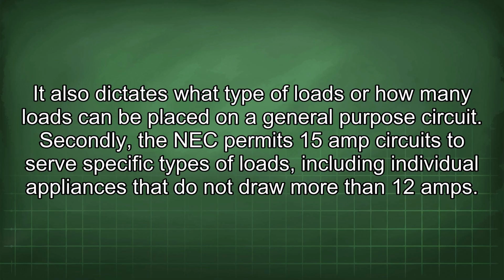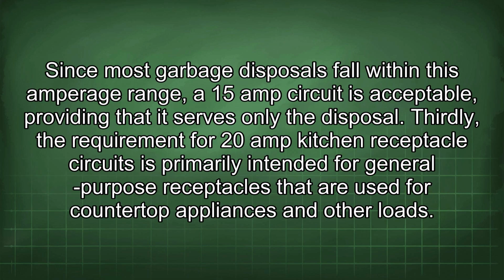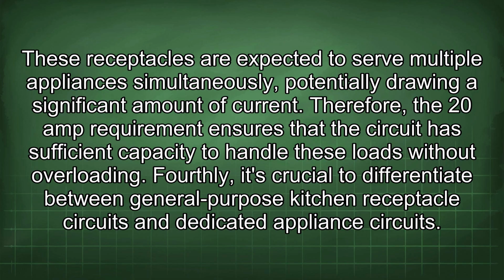Secondly, the NEC permits 15-amp circuits to serve specific types of loads, including individual appliances that do not draw more than 12 amps. Since most garbage disposals fall within this amperage range, a 15-amp circuit is acceptable, providing that it serves only the disposal. Thirdly, the requirement for 20-amp kitchen receptacle circuits is primarily intended for general-purpose receptacles that are used for countertop appliances and other loads. These receptacles are expected to serve multiple appliances simultaneously, potentially drawing a significant amount of current. Therefore, the 20-amp requirement ensures that the circuit has sufficient capacity to handle these loads without overloading.